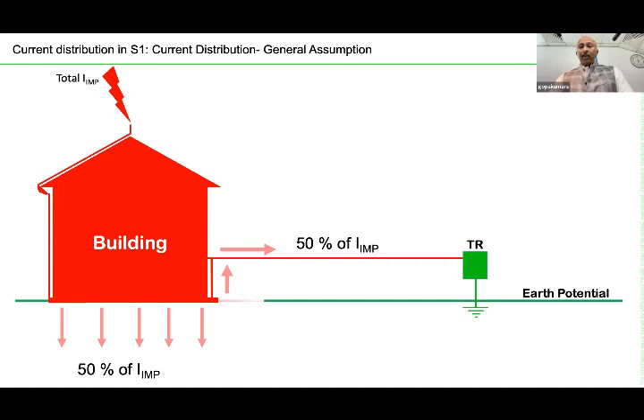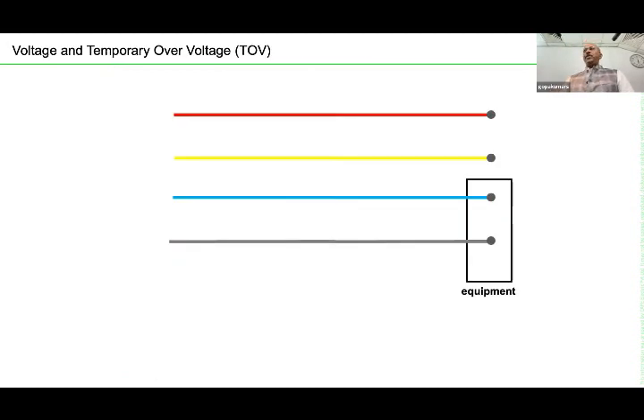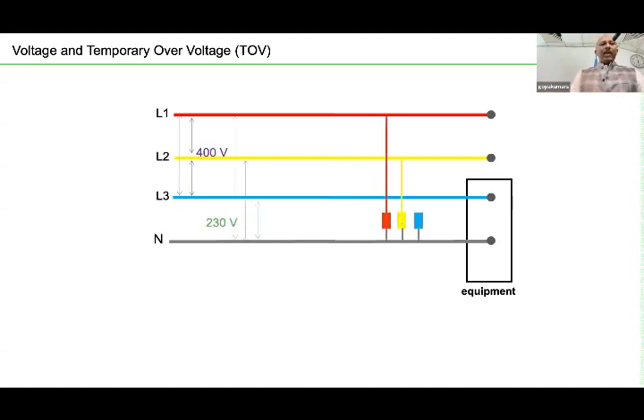Once you install an SPD, let us say, for example, one typical problem which is faced in India. I am just showing you a 3-phase and maybe a single-phase equipment connected to a 3-phase. Now, very simple explanation. Line to line, you have 400 volt. Line to neutral, you have 230 volt. And imagine you have 3 SPDs between line to neutral. At 230 volt, the SPDs are very good.